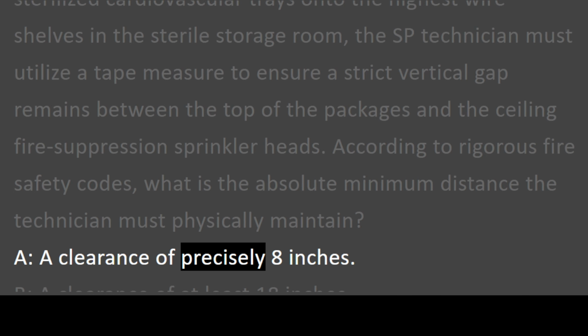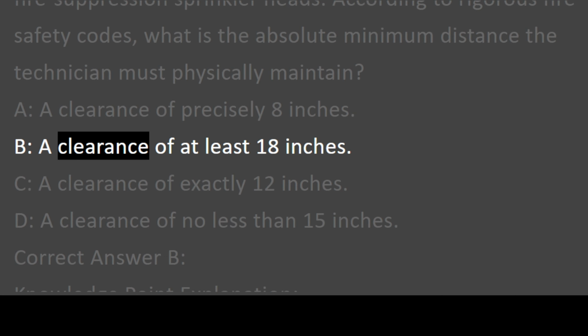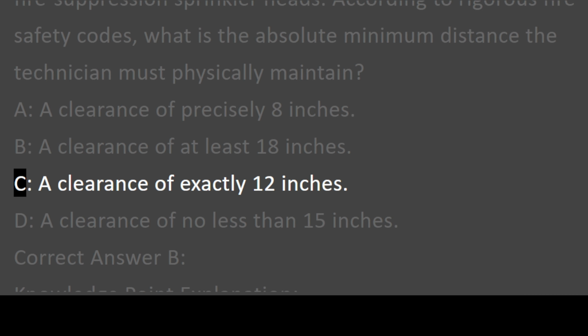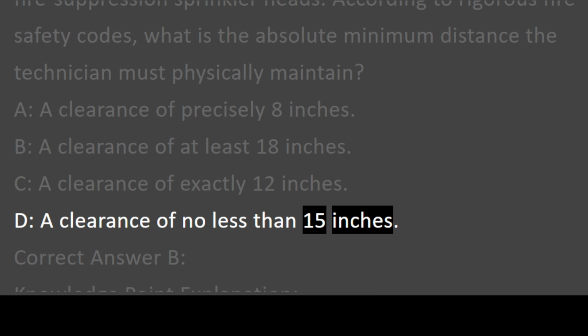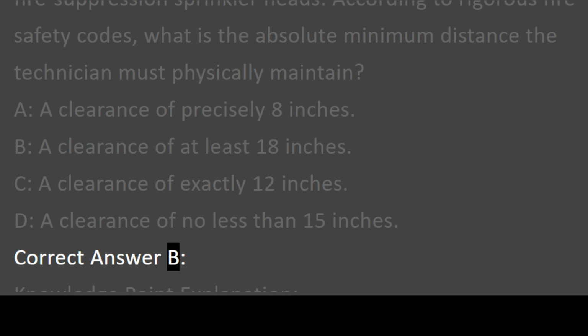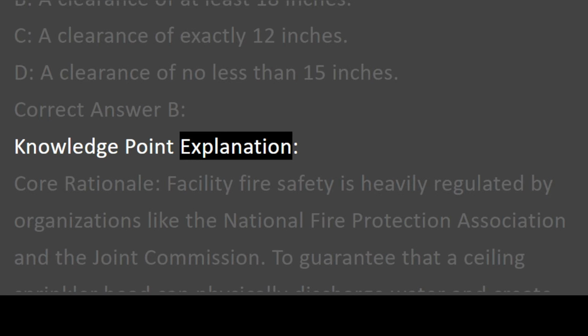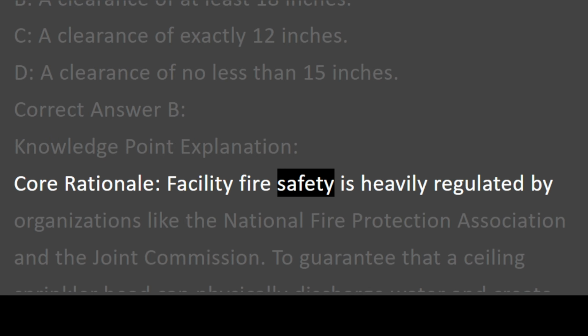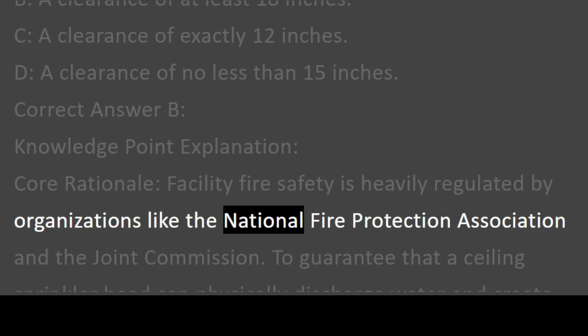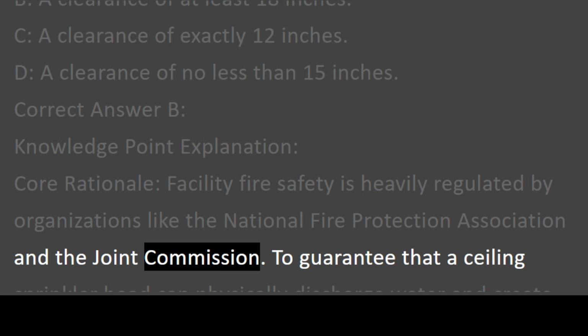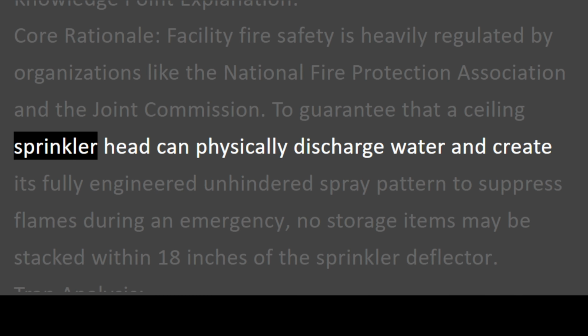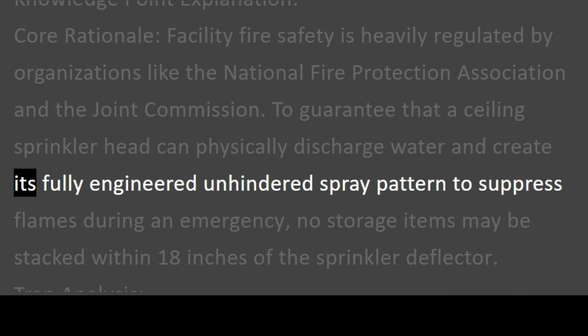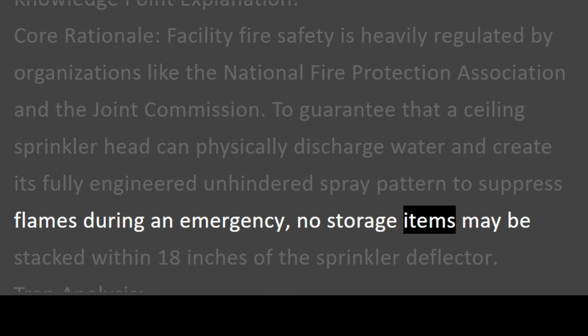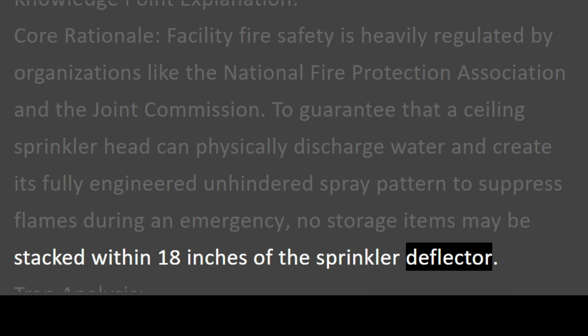A. A clearance of precisely 8 inches. B. A clearance of at least 18 inches. C. A clearance of exactly 12 inches. D. A clearance of no less than 15 inches. Correct answer B. Knowledge point explanation. Core rationale. Facility fire safety is heavily regulated by organizations like the National Fire Protection Association and the Joint Commission. To guarantee that a ceiling sprinkler head can physically discharge water and create its fully engineered unhindered spray pattern to suppress flames during an emergency, no storage items may be stacked within 18 inches of the sprinkler deflector.